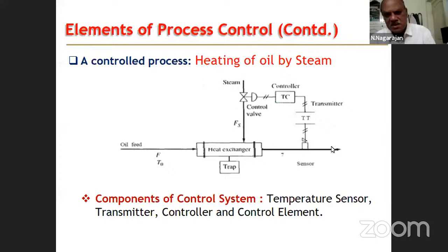Depending upon the variation, if it suddenly goes to, let us say, 160 degrees centigrade, then the controller will measure the 160 and compare it with the set point of 150. There is 10 degrees more temperature in the outlet, so it will start closing the steam valve. It will allow less steam to the heat exchanger till it comes down to 150. Similarly, if it is less than 150, say 140, the controller will open the steam valve more and allow more steam to go into the exchanger, and it continues until you reach the 150 point. So this is how the process is controlled. This is a continuous control loop. It is happening continuously in the process.